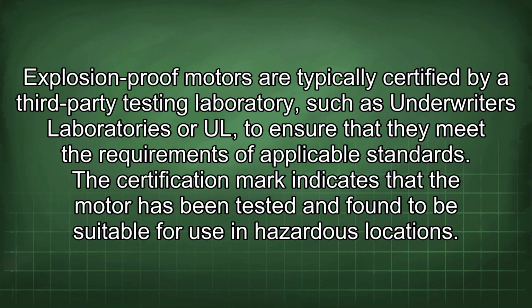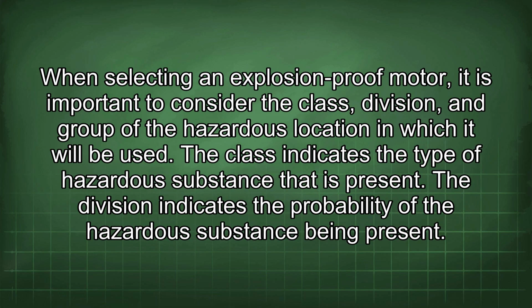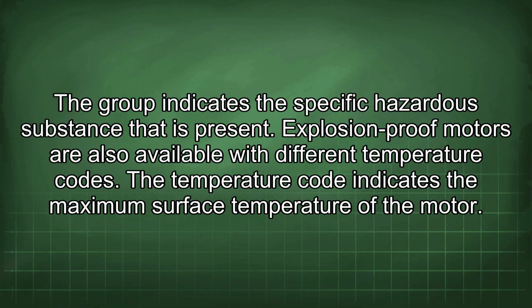Explosion-proof motors are typically certified by a third-party testing laboratory, such as Underwriters Laboratories or UL, to ensure that they meet the requirements of applicable standards. The certification mark indicates that the motor has been tested and found to be suitable for use in hazardous locations. When selecting an explosion-proof motor, it is important to consider the class, division, and group of the hazardous location in which it will be used. The class indicates the type of hazardous substance that is present. The division indicates the probability of the hazardous substance being present. The group indicates the specific hazardous substance that is present.